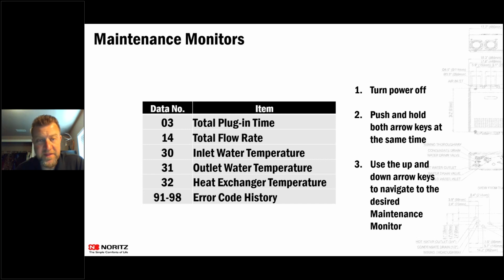Like the other day, I had a guy that added a recirc pump to a tankless water heater, and he says, hey, this recirc pump is not working. The unit won't kick it on. Nothing's working. It's not heating the water. The burner won't turn on. So we had him go to maintenance monitor 14. He turned on the pump, and maintenance 14 just kept showing zeros. So the unit was not sensing flow through that pump. Turns out the pump that they bought was just a small little half-inch pump that could not pump water through the house, so it wasn't even pushing flow through the unit, so they had to upsize to a bigger pump. But those are things you can look at to see.